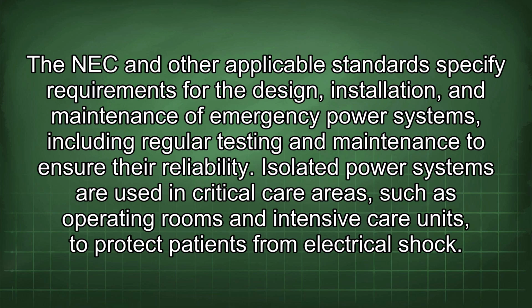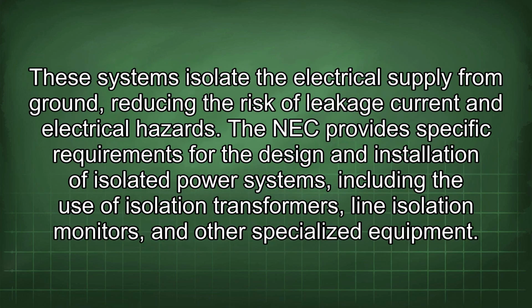Isolated power systems are used in critical care areas, such as operating rooms and intensive care units, to protect patients from electrical shock. These systems isolate the electrical supply from ground, reducing the risk of leakage current and electrical hazard. The NEC provides specific requirements for the design and installation of isolated power systems, including the use of isolation transformers, line isolation monitors, and other specialized equipment.